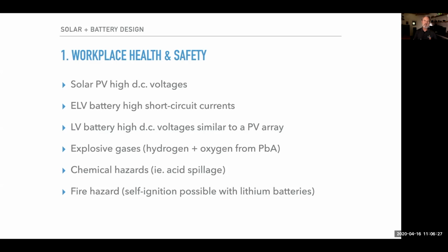LV batteries, of course, now you've moved above 120 volts DC and you're required to have a lot more protection. Now, there's a new battery standard that's come out recently. It was published last year. It's been enforced in Australia now, and it's kind of soft enforced in New Zealand. So it's still a little bit ambiguous in New Zealand how the new battery standard is applied, AS/NZS 5139. But what it does say is anything over 60 volts is deemed to be hazardous. So it's lowered that bar quite a lot. And for good reason, because in damp environments, even a 60 volt battery system can potentially be a shock hazard.